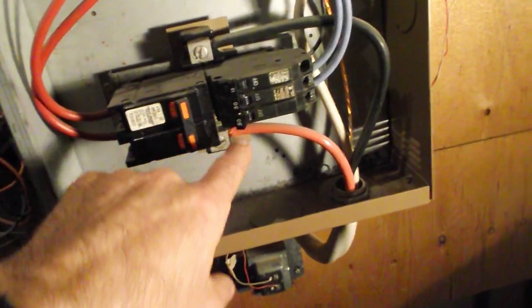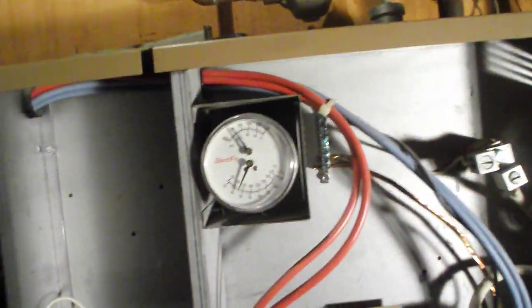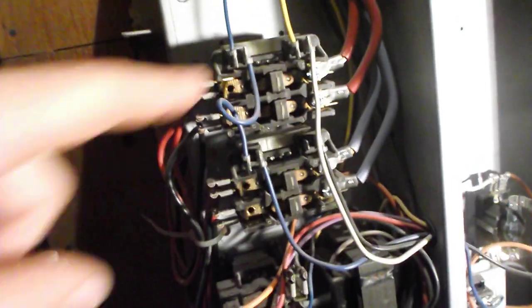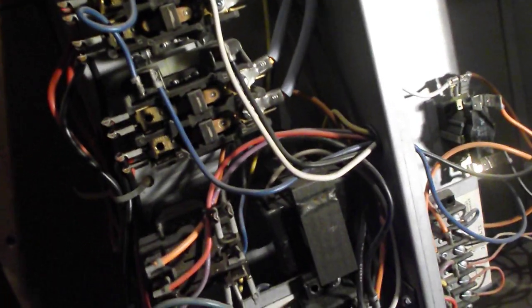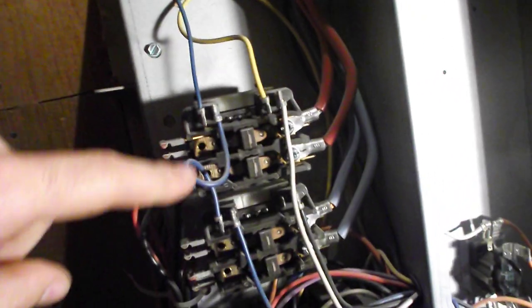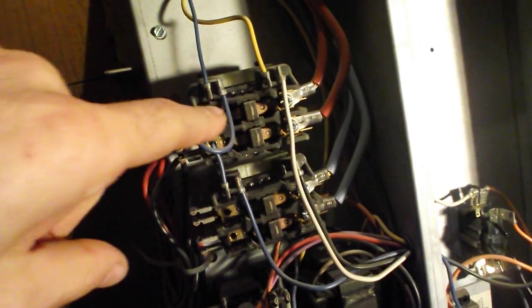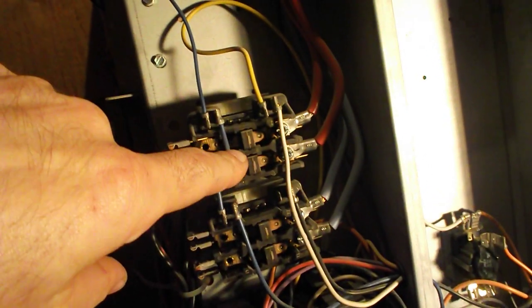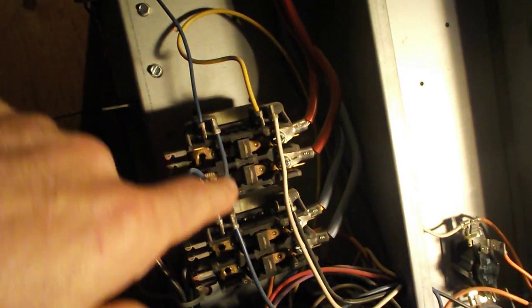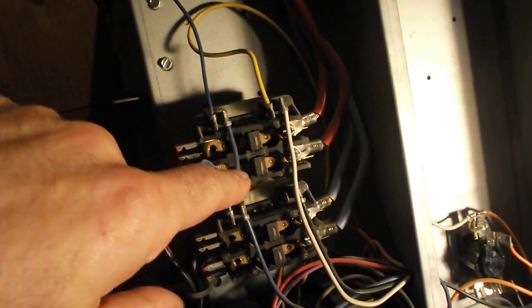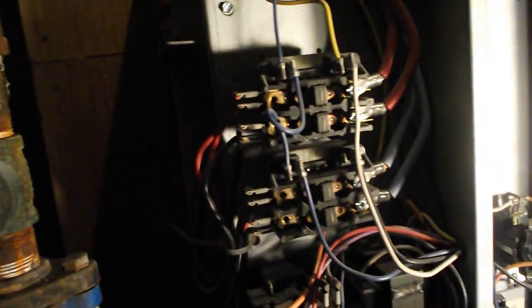So with these covers off, you can see the two smaller breakers and then the two larger breakers, and then they have two nicely different colored sets of gauges of wires that come over to this contactor panel right here. These are the two contactors. It's running right now, so I was going to engage these manually to show them cutting in. There, right at the end of my finger, are plastic nibs. They're not electrical contacts, but if you poke a non-conductive plastic screwdriver on those tabs, you can artificially trigger those contactors to cut in.